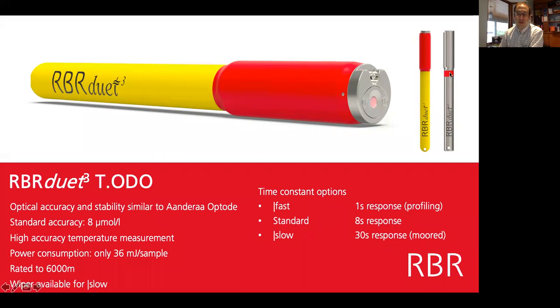Again, this can be a slow sensor, so you can put a wiper on it, and it can be configured such that it will run for 2.5 years, making an oxygen and temperature measurement every 10 minutes. So it's very low power. It's quite small, and it will run for 2.5 years at that 10-minute measurement interval.